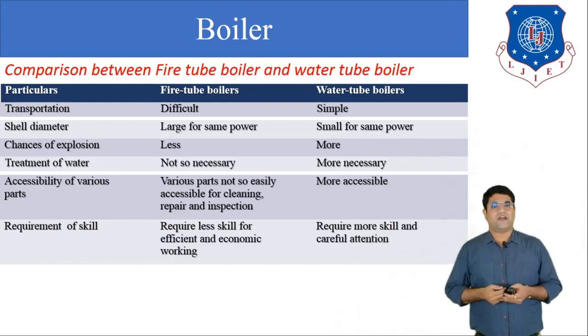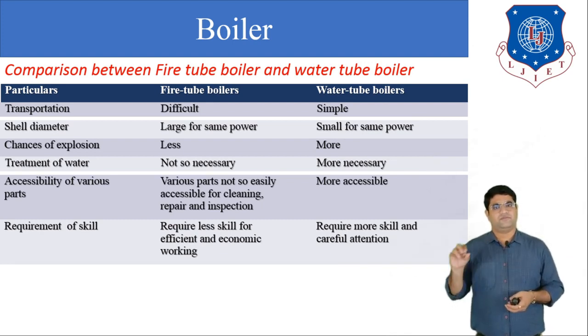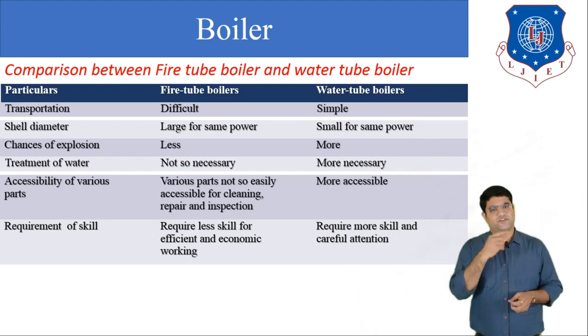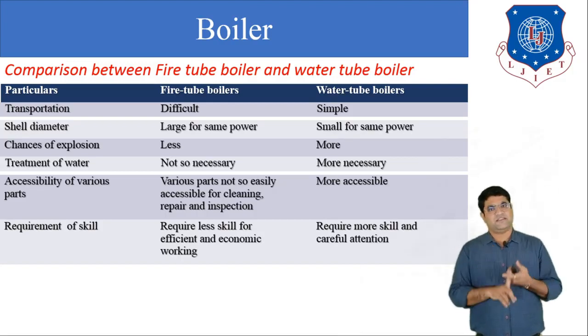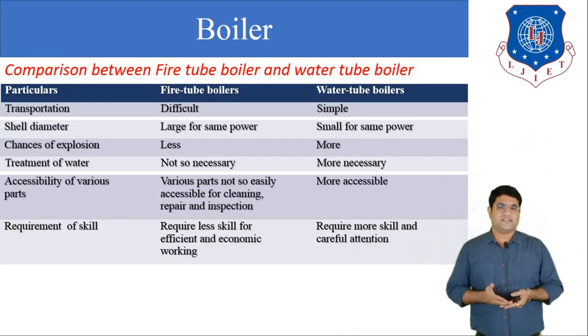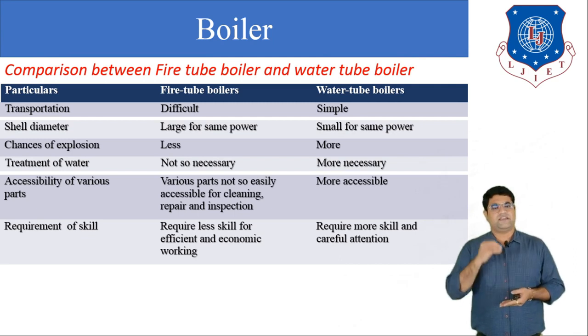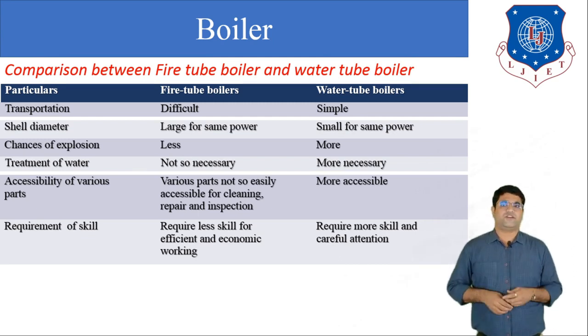Okay, so in the fire tube boiler we get the benefit that we do not have to filter the water. So we can say that the treatment of the water is not necessary in the case of the fire tube boiler. Now in the water tube boiler, we know that the water travels inside the tubes, so there is a chance of salt deposition inside the tube. And if the salt is deposited inside the tube, then there is a chance that the heat will not be transferred. So we can say that the treatment of the water is very much necessary in the case of the water tube boiler.